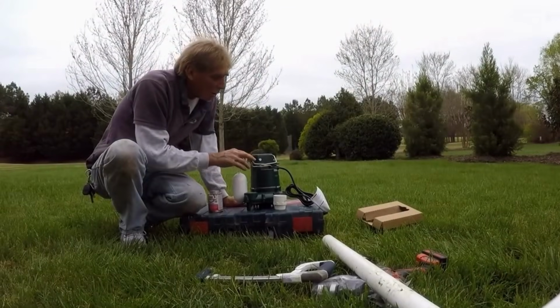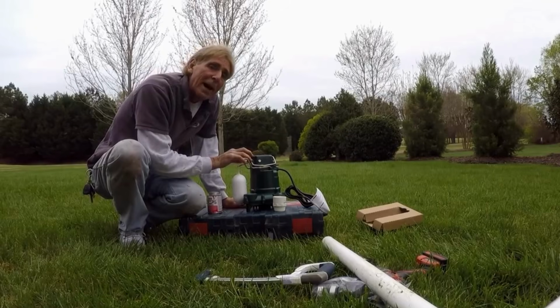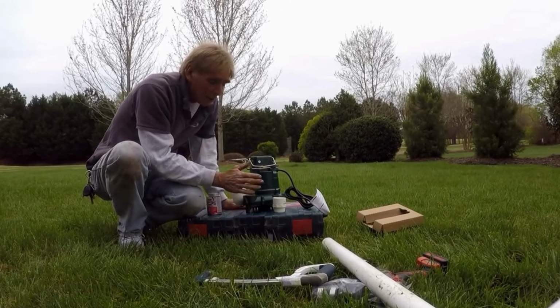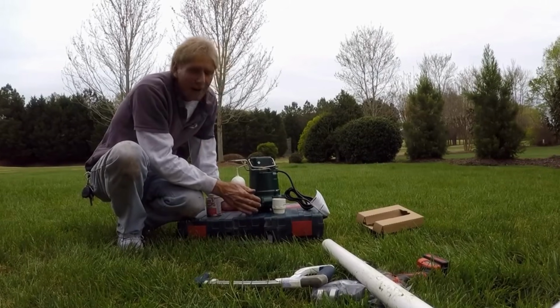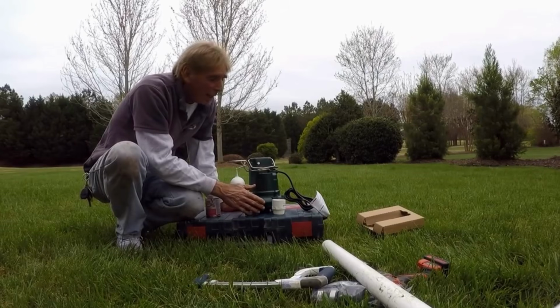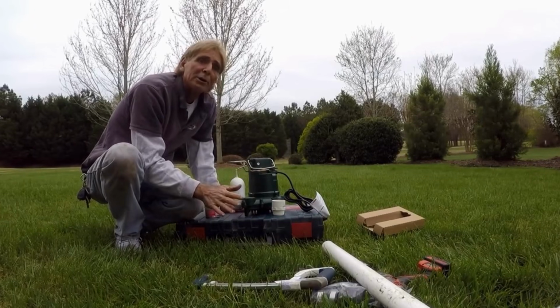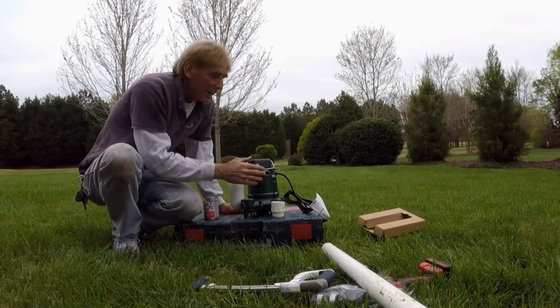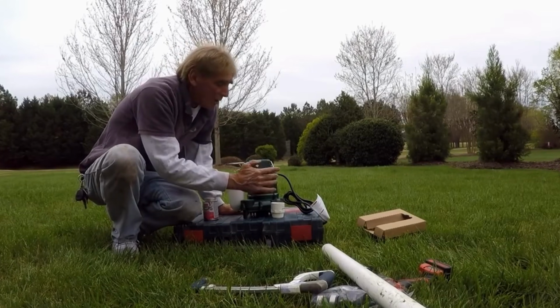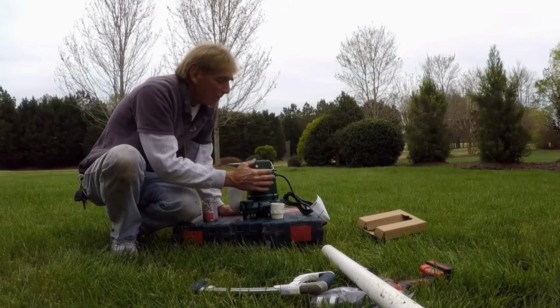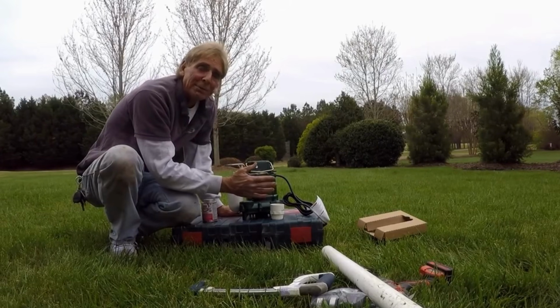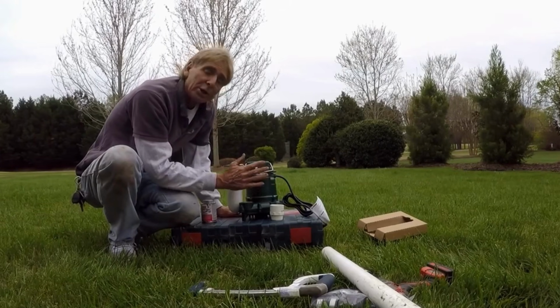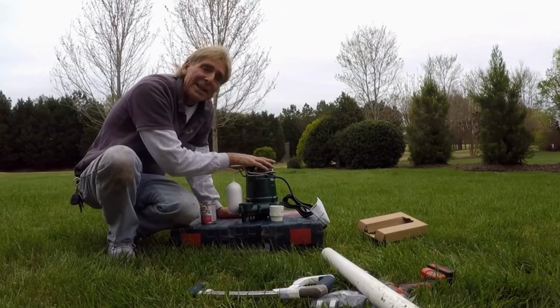Now we're setting up the Zoeller M53. They call this the Mighty Mate, and what a great name. This is 1/3 of a horsepower. It pushes about 40 to 50 gallons per minute, and it's the same as any other 1/3 horsepower on how much it pushes. But the difference is that this pump is made of cast iron, not one of those stainless steels or the polypropylene injected plastics. And the reason that's so good is because it acts as a heat sink.